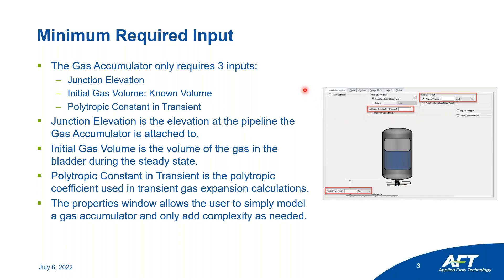Junction elevation is the elevation at the pipeline the gas accumulator is attached to, which you can see here with this dimension line. The initial gas volume is the volume of the gas in the bladder during steady state, and the minimum input for that is a known volume for steady state entered directly. The polytropic constant in transient is the polytropic coefficient used in the transient gas expansion and contraction calculations, and we'll talk about that more a little later.